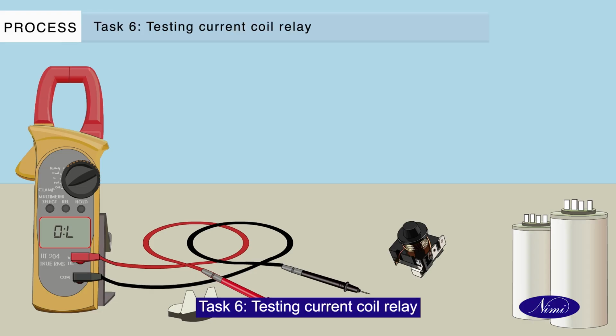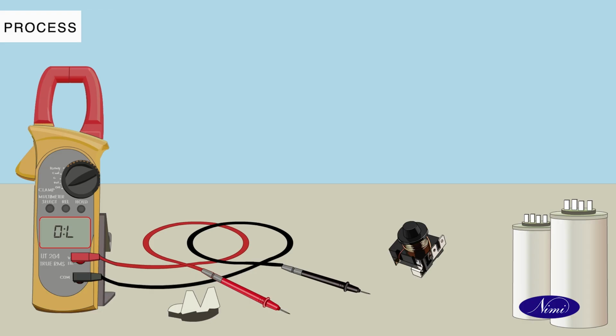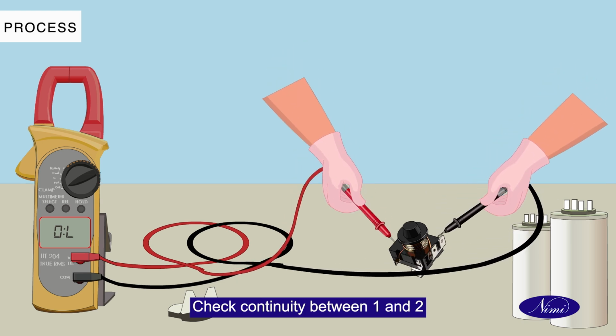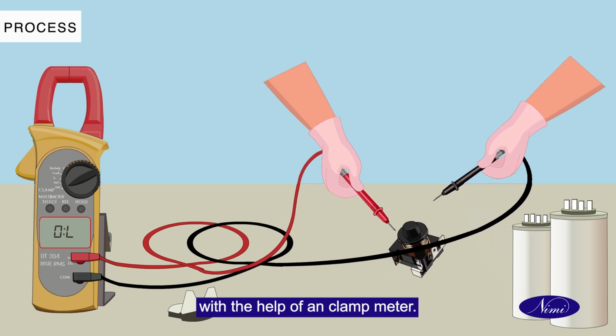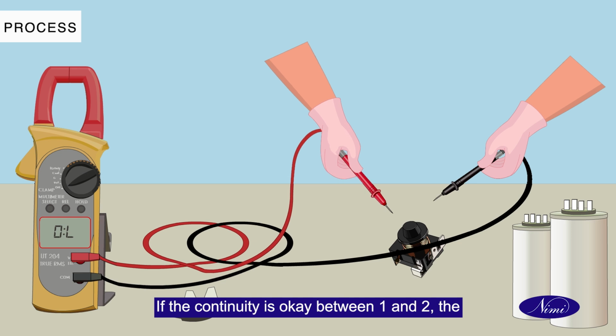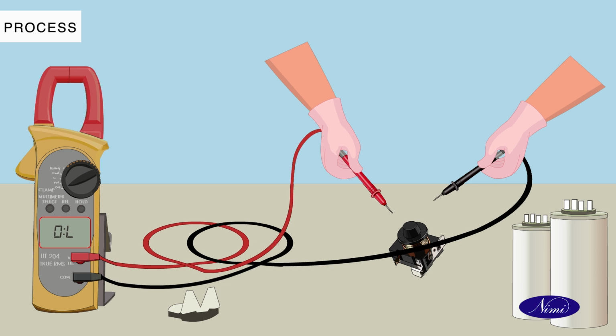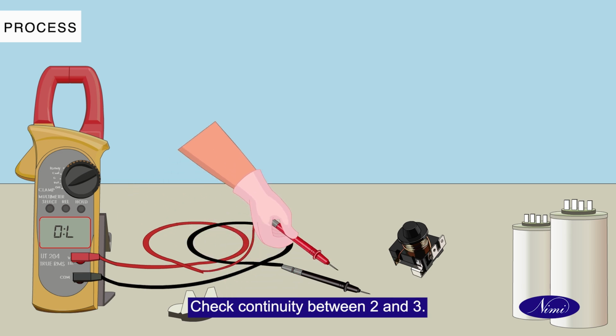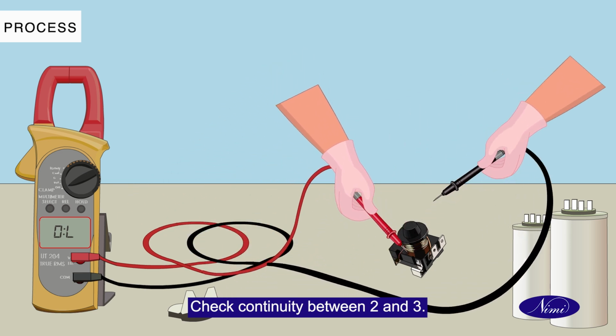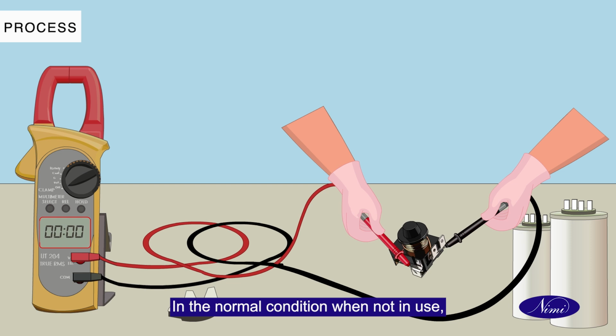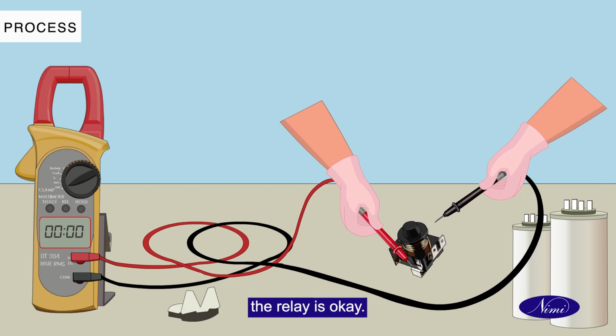Task 6. Testing current coil relay. Check continuity between 1 and 2 with the help of a clamp meter. If the continuity is okay between 1 and 2, the coil continuity of the current coil relay is okay. In the normal condition, 1 and 2 continuity will be there. Check continuity between 2 and 3. In the normal condition, when not in use, 2 and 3 are open. If there is no continuity between 2 and 3, the relay is okay.